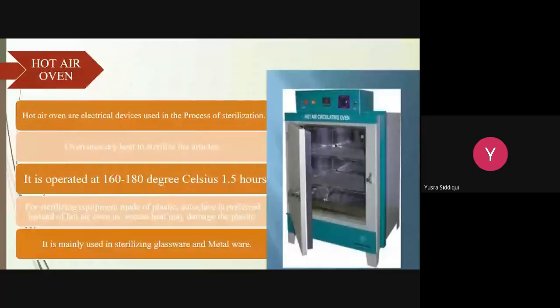As we know, the hot air oven is commonly used for dry heat sterilization, which is a method of controlling microorganisms. It employs a higher temperature in the range of 160 to 180 degrees centigrade and requires an exposure time of up to 2 hours depending upon the temperature employed. The benefits of dry heat include good penetrability and non-corrosive nature, which make it applicable for sterilizing glassware, metal, and surgical instruments. It is also used for sterilizing non-aqueous thermostable liquids and thermostable powders.